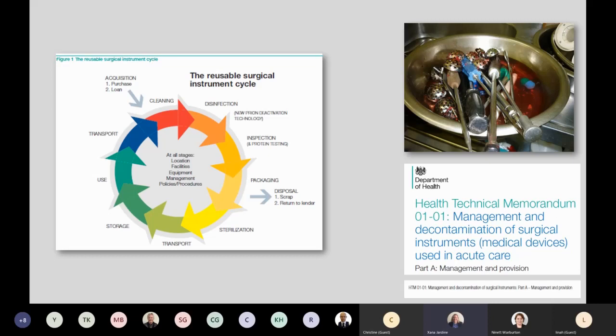That may cover how you're supposed to reprocess, for example, a laryngoscope blade, how to manage your eye instruments, or what the sterilization time is for a particular device. I once was lecturing at the Eye Congress and looked at pertinent information around some eye instruments, and it clearly stated the sterilization time needed to be 4 minutes. I know numerous hospitals have their sterilization time set at 3.5 minutes, and these are pertinent factors we need to bear in mind.